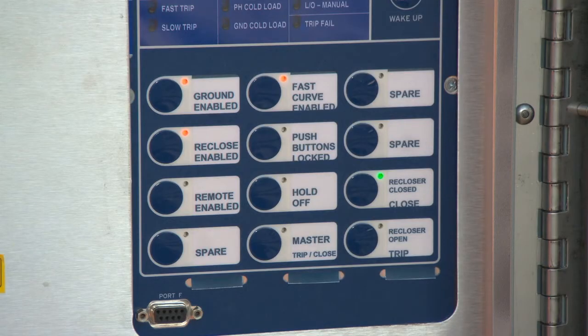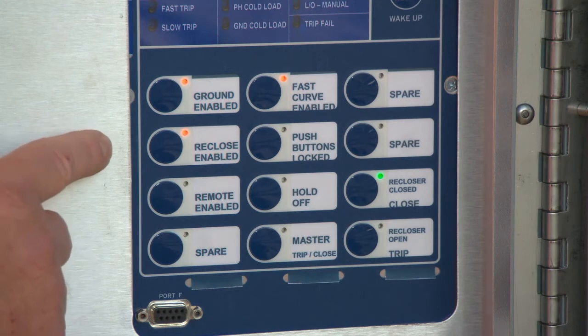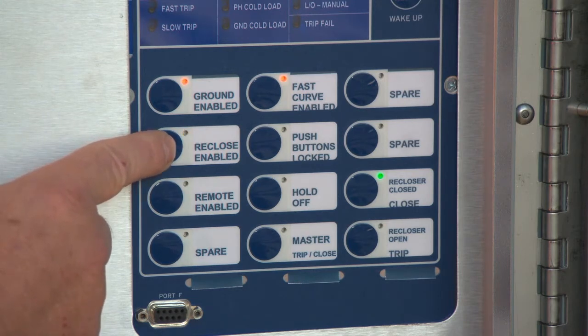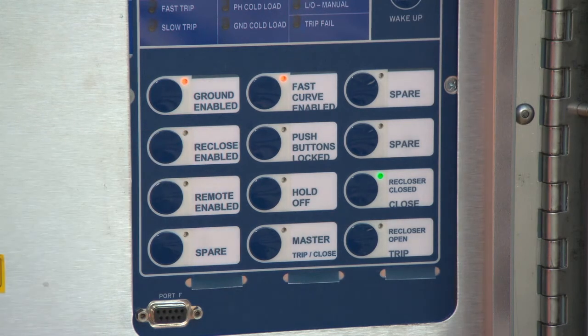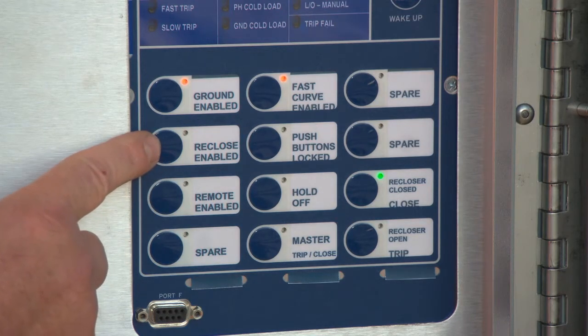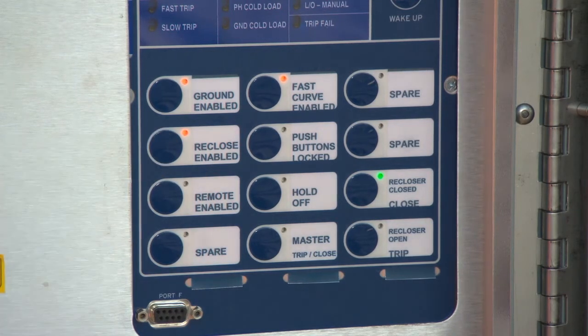The Reclose Enabled button will deactivate the normal multi-shot reclose process if it is turned off. This means that the recloser will operate with 1 shot until lockout. This is not to be used as a hold-off substitute. It is for testing purposes only. To re-enable the normal multi-shot reclosing process, press the Reclose Enable button so that the amber LED will light up.